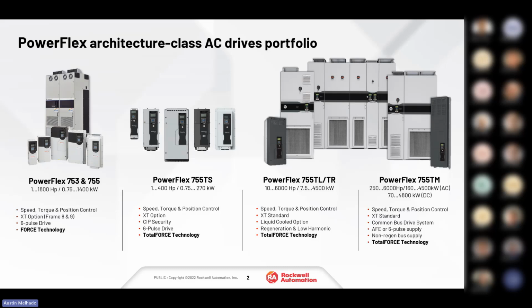The TL and TR are an active front end drive, so they're not your standard 6-pulse drive. They have 6 IGBTs in the front, and we'll talk a little bit about the differences on the next slide. With the active front end, they're able to mitigate low harmonics on the front end of the drive and also able to do regen back onto the line. The TR would be the regen low harmonic VFD, and the TL would just be the low harmonic. The TM is a common bus supply drive. It could be made up of regen and non-regen drives, so it could have multiple styles of the 755, and that would be a common bus system VFD.